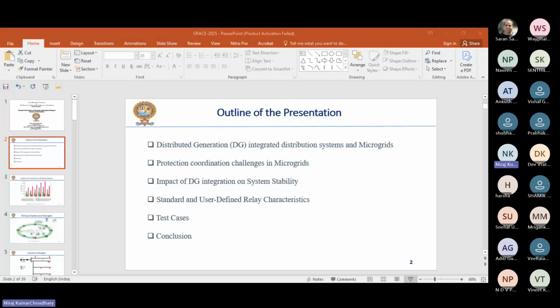the relevance of this topic, protection coordination, in terms of number of publications in the past few years, where different types of protection coordination schemes have been used, starting from conventional protection devices, then adaptive protection schemes, multi-agent based protection schemes, data mining based schemes, blockchain based protection schemes, and user defined characteristics based protection schemes. You can see that among all these, the number of publications on user defined relays is continuously increasing. It means you have flexibility to adapt with the system configuration. You can modify your relay characteristics as per your requirement, right?